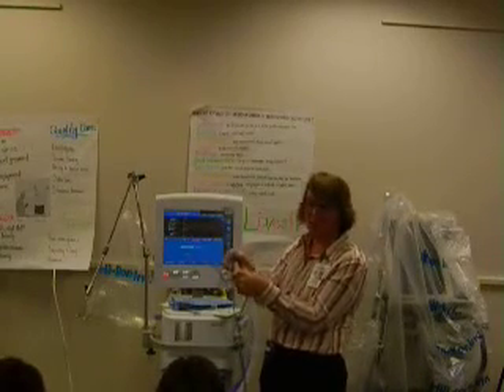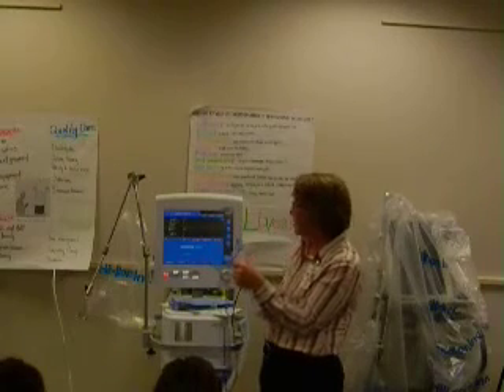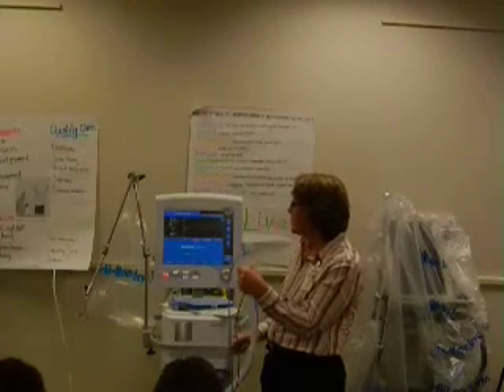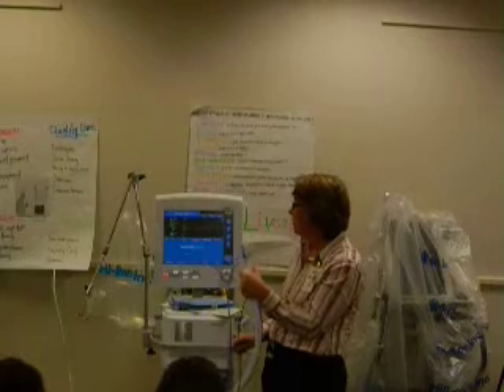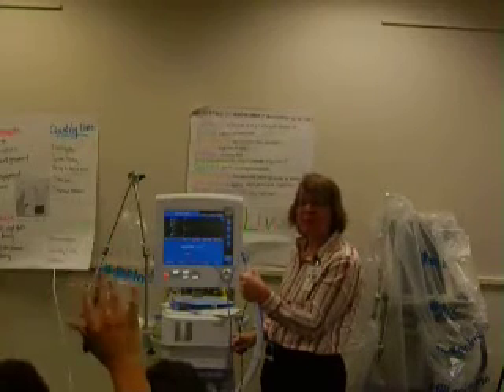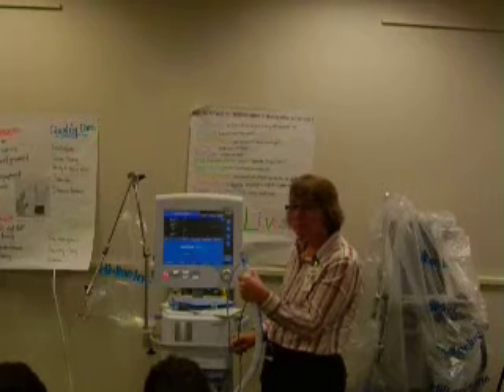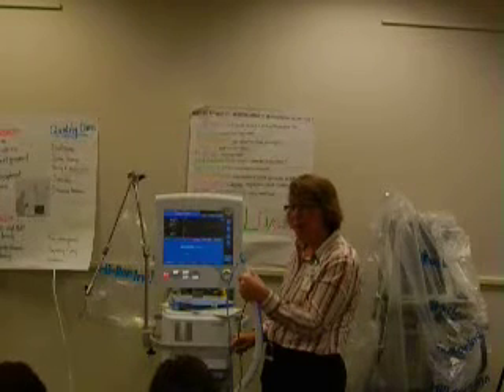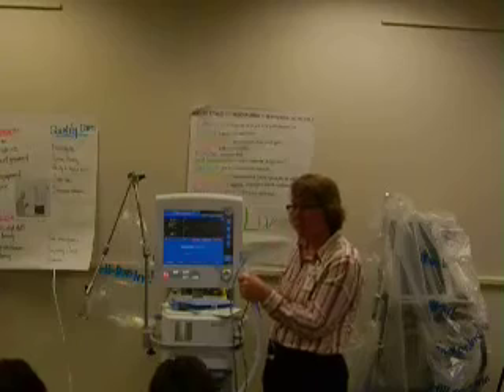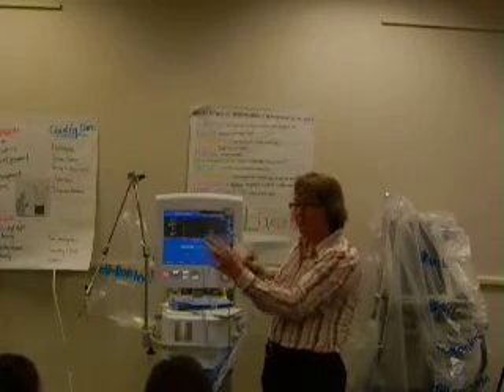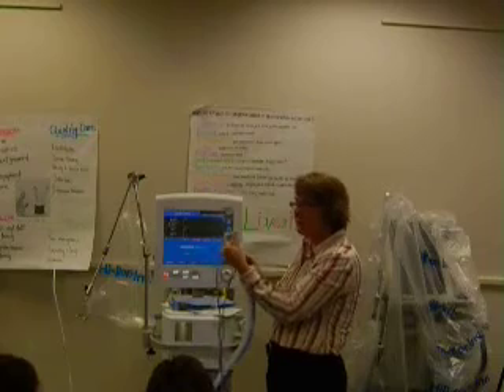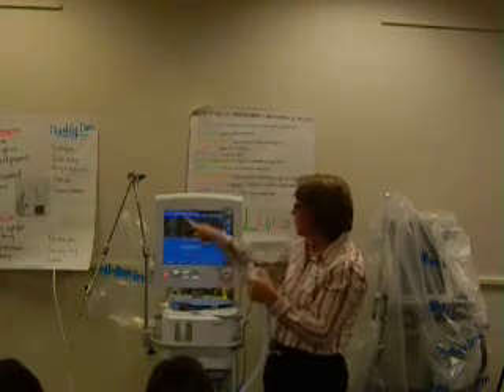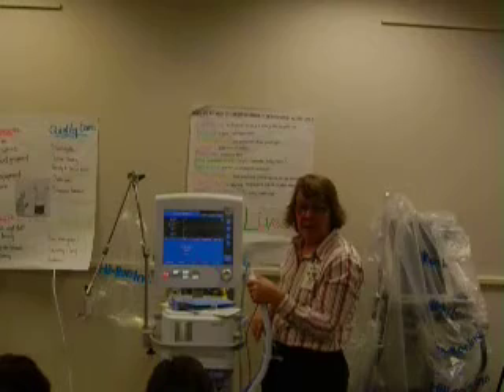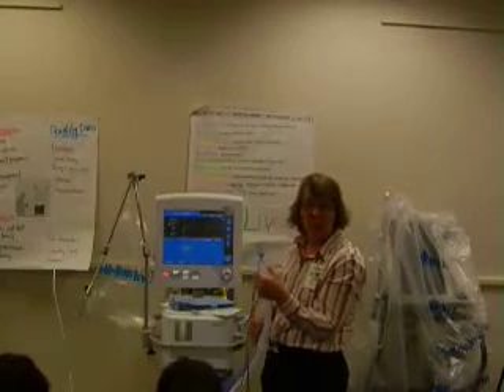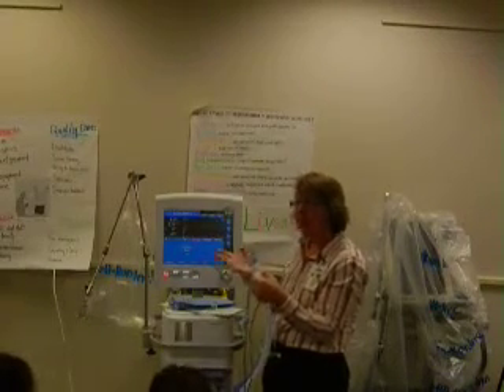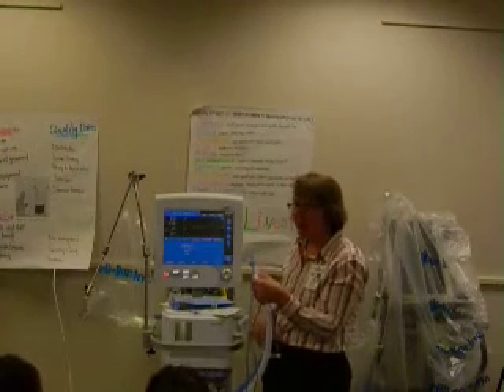Now turn flow sensor, it wants you to put it back the way you had it. So now we put the blue back towards the patient. As soon as you do that, it knows, and it'll continue on its calibration. Prior to turning it, is there a right way and a wrong way that it needs to be set at? The blue has to go towards the patient. Blue, right here, see? Blue and clear. Blue goes towards the patient. Flow sensor calibrated, okay, we're done. Sometimes they don't calibrate because something's wrong with them, you just get another one. Try it twice. If it doesn't calibrate, then get another one and try it again. A whole other flow sensor.